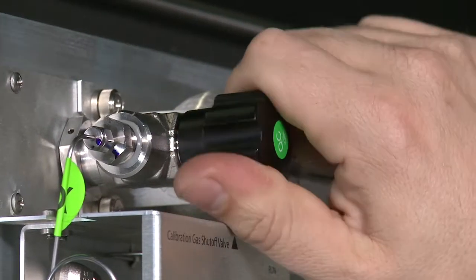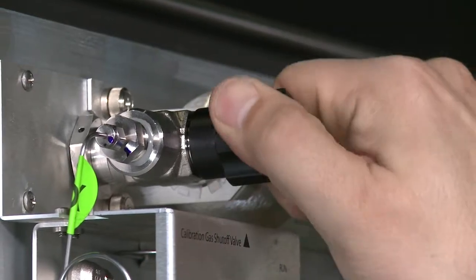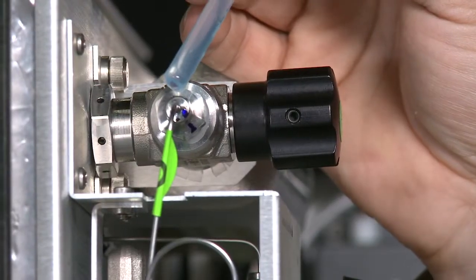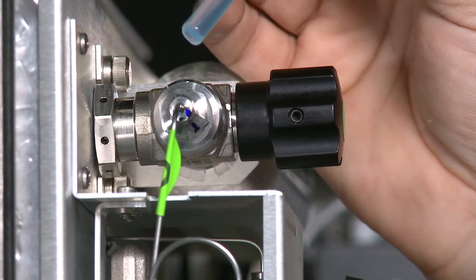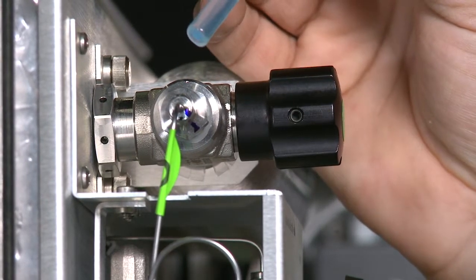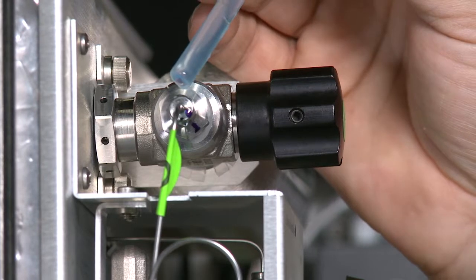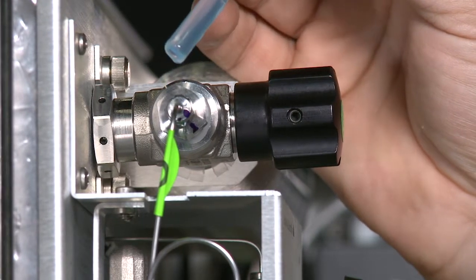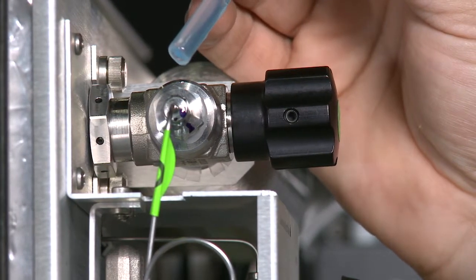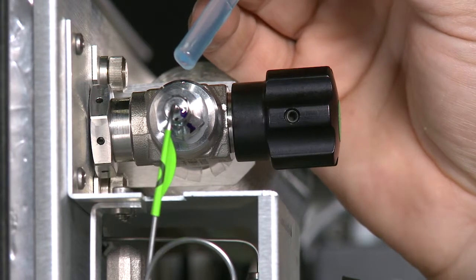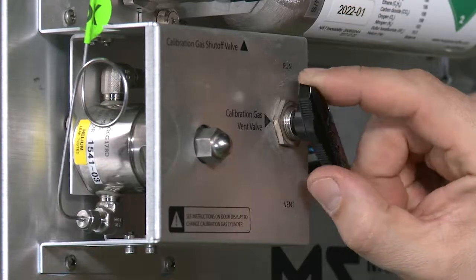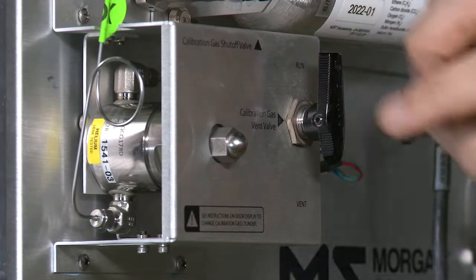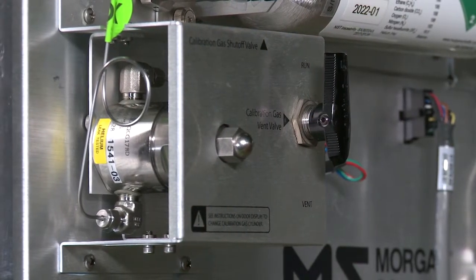Slightly open the cylinder shutoff valve, then close it as quickly as possible to pressurize the system. Use a helium detector or leak detection fluid to ensure that the connections are leak tight. If a leak is detected, tighten the nut 1/16 to 1/8 of a turn. When everything is leak tight, turn the valve to the vent position.